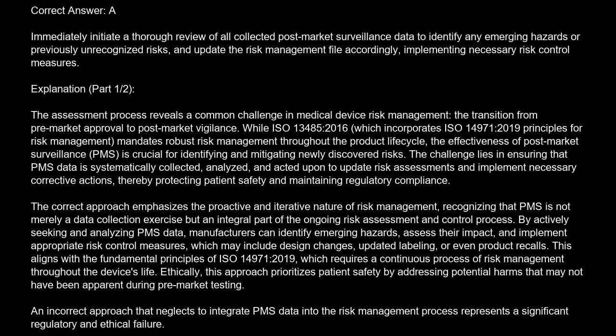By actively seeking and analyzing PMS data, manufacturers can identify emerging hazards, assess their impact, and implement appropriate risk control measures, which may include design changes, updated labeling, or even product recalls. This aligns with the fundamental principles of ISO 14971:2019, which requires a continuous process of risk management throughout the device's life. Ethically, this approach prioritizes patient safety by addressing potential harms that may not have been apparent during pre-market testing.